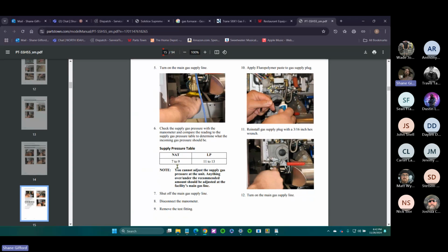If your natural gas supply pressure to your manifold is 15 because you have a failed regulator, this thing is going to be shooting out flames like crazy. Even if you have it set to 4 inches water column, because the back pressure is so high, it's going to force that pressure through. And now you're going to be burning at like 8 inches water column.